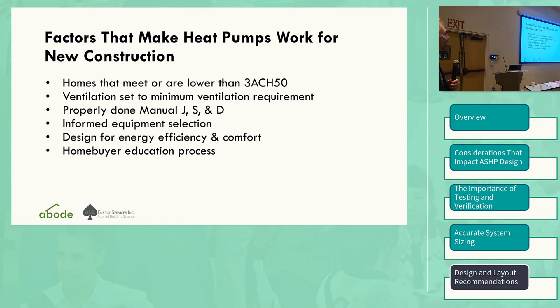Factors that make heat pumps work for new construction: homes that meet code for air changes, that's number one. Ventilation set to the minimum requirement. Properly done Manual J, S, and D. Informed equipment selection. Design for energy efficiency and comfort, keeping that in mind while talking with the builder and communicating well, saying we want it energy efficient but also comfortable, from the beginning.